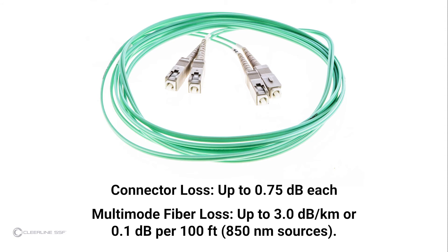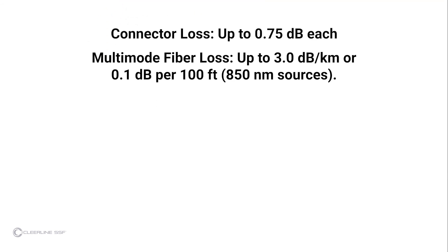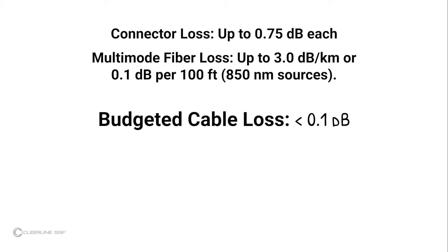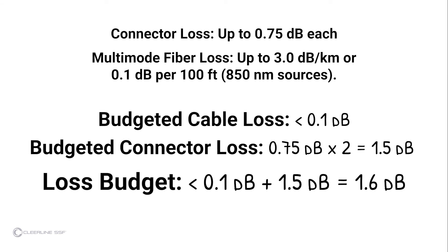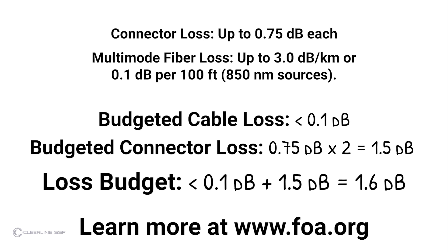For multi-mode fiber, the loss is about 3.0 decibels per kilometer for 850 nanometer sources, or 0.1 decibels per 100 feet. In this video, the cable under test is quite short, so the cable loss calculation is less than 0.1 decibels. The loss calculation for the connectors is 1.5 decibels — 0.75 decibels per connector times 2 connectors. The test result is less than 1.6 decibels, so the cable passes industry standards for link loss. Refer to the included Fiber Optic Association guidelines or visit the FOA on the web for further information on fiber testing or installation.